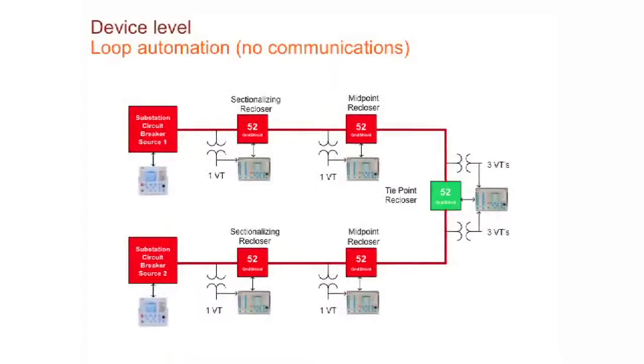So I'm going to go through some of those applications. This is a typical substation. You have your 2 breakers at the substation with IEDs. Outside of the substation, you have a sectionalizing recloser, a midpoint recloser, a tie point recloser, and the same on the other feeder. So for example, you have a fault between the sectionalizing recloser and the midpoint recloser. This is a voltage-based automatic restoration scheme, so you don't need any communications. We have a lot of customers that implement that. The important part here is to have two things: voltage inputs, and the logic embedded in the device to execute the restoration scheme.